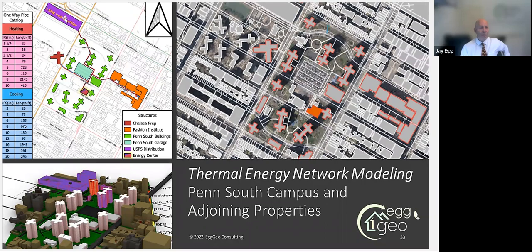Those 8 megawatts - you can see our scientists and engineers put some pipe sizes here for what's going to run across, though that's not important. If we can turn off those cooling towers and pipe that energy through a thermal energy network over to the central energy plant, guess what? They're going to be able to turn off those boilers. That entire 4 megawatts of thermal energy need for Penn South, for those 2,500 families, is offset and to spare.